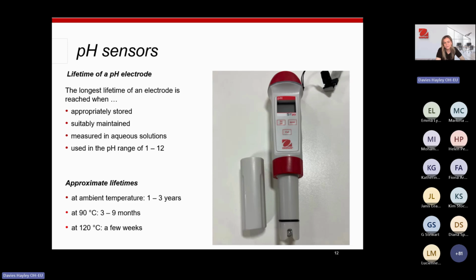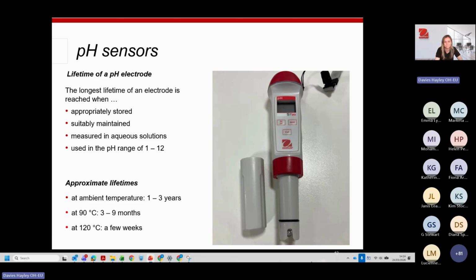And the reason the temperature affects it is because, as we mentioned, the membrane or the tip has a lovely gel layer that's ion rich. If you're submerging your electrode into samples that are high temperature, that gel layer is going to become damaged and frail, it's going to become dry and crispy, and it's going to deteriorate quite quickly in high temperatures.